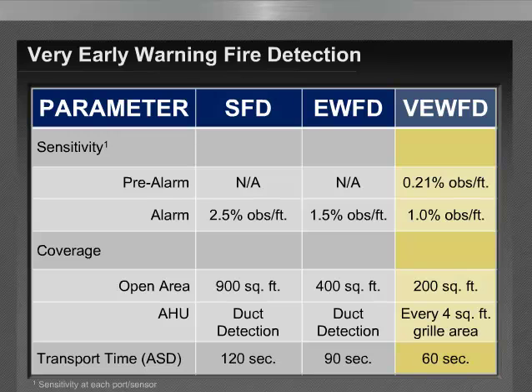For very early warning fire detection, alarm sensitivity is specifically 1% obscuration per foot. I might note, and this is relevant to each and every one of the sensitivity classifications, that sensitivity is at the detector or port, meaning that each and every sampling port must be at 1% obscuration per foot or better under the sensitivity classification. Unlike the previous two classifications, very early warning fire detection is expected to provide a pre-alarm signal. We haven't seen that in the other sensitivity categories, and this is specifically set at 0.21% obscuration per foot. And when we look at spacing, we've come down from 900 square feet for standard fire detection, 400 square feet for early warning fire detection, and we're now down to 200 square feet for very early warning fire detection.